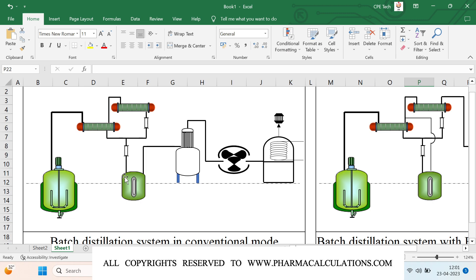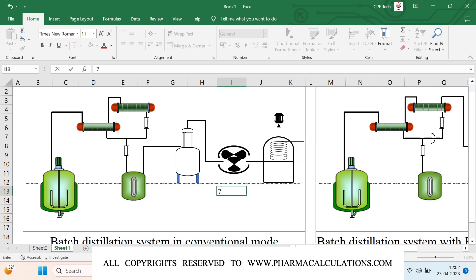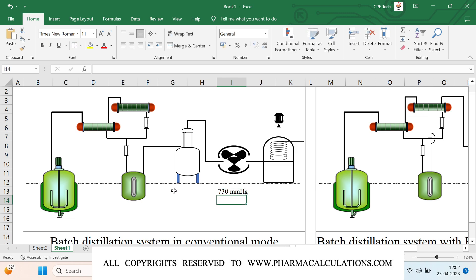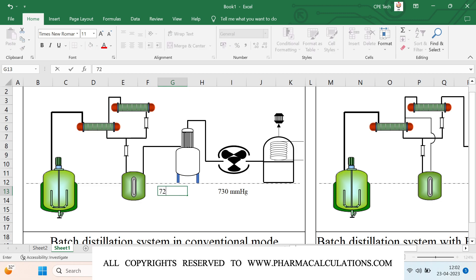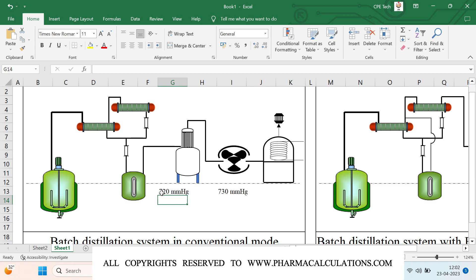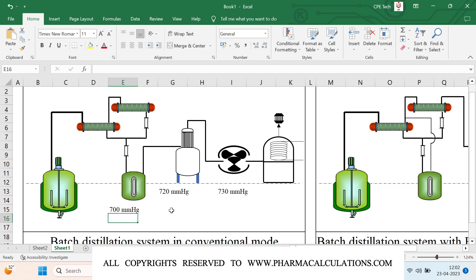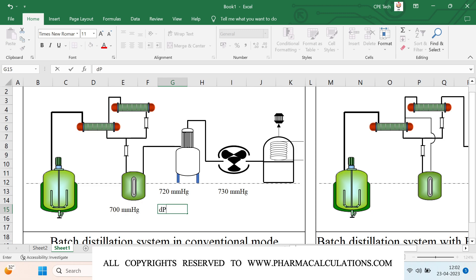Due to this difference in heights, there is some pressure generated by the flow of distillate. Because of this pressure, the vacuum being generated in the receiver by the vacuum pump gets lowered. For example, if about 730 mmHg of vacuum is being generated, after entering the pre-condensing trap it gets reduced to 720 mmHg due to the presence of uncondensed vapors, and it may reduce somewhat further at the distillate collection receiver. You can calculate this pressure using the formula: ΔP = ρ × g × H.